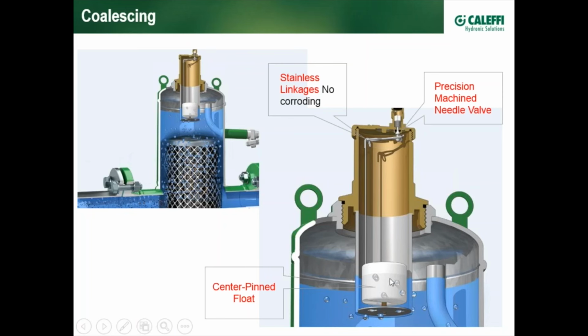The water level drops, the float drops with it, and connected to the float is a linkage that pulls down this little needle valve. Now, a couple of things that are very attention to detail related: stainless steel linkages rather than plated steel that some makes have, so non-corroding. A float that is pinned. We don't allow any chance for the float to come in contact with the ID of the cylinder it rides within. It doesn't take much frictional force to hang up floats. We don't give it a chance.